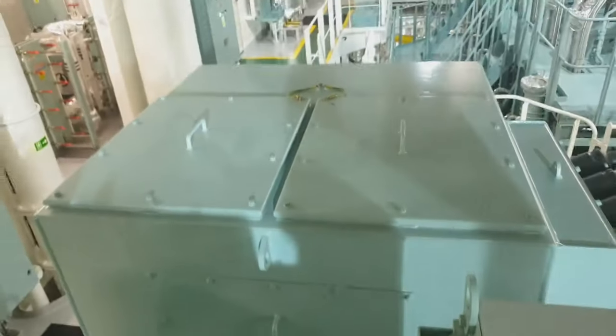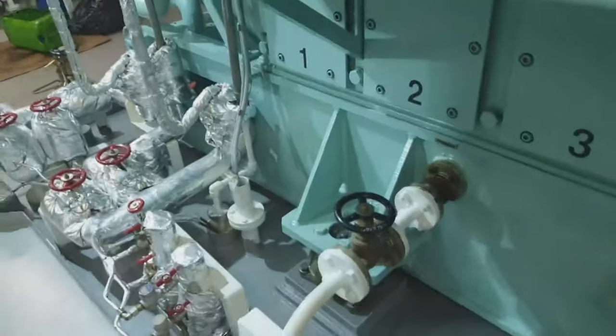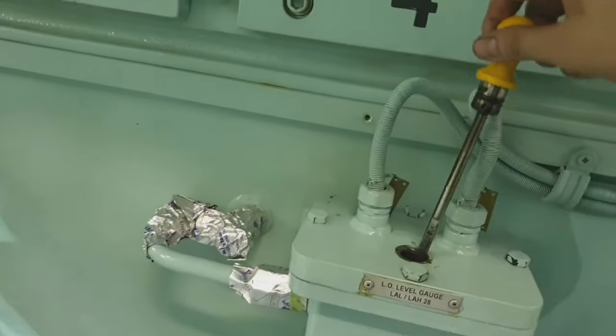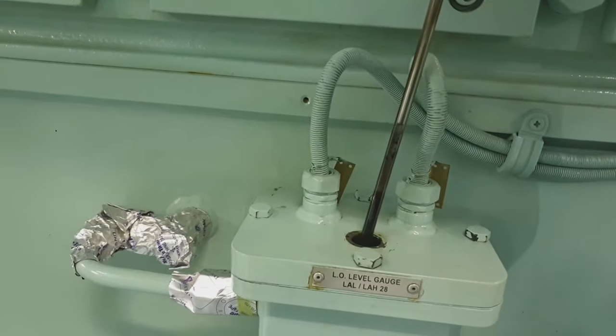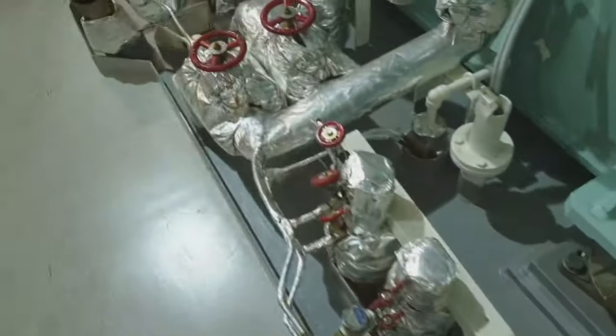This is the top assembly of the engine. And this is the governor. Here it is, the governor oil. It has to be checked daily, guys. And this side is the alternator. This is the 3-phase alternator, guys, the AC generator. So this is the lube oil dipstick, lube oil gauge, and it also has the low level and high level alarm monitoring. These valves are the fuel valves, the diesel and heavy fuel oil, and that is the duplex filter.